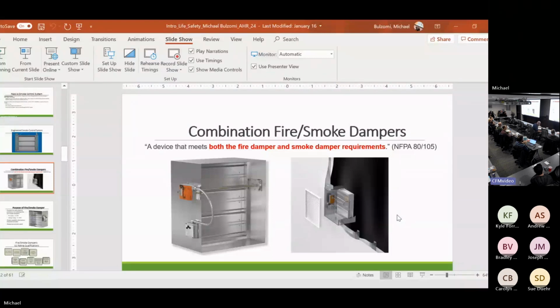Let's talk about fire smoke dampers real quick. Before a fire smoke damper, if you had a shaft wall or a barrier that required both smoke protection and fire protection, you put a fire damper in the opening and a smoke damper behind it. We came up with a single device that meets the needs and requirements of both. It's tested to both standards. At the end of the day, it's a fire damper. I can use it for smoke control.